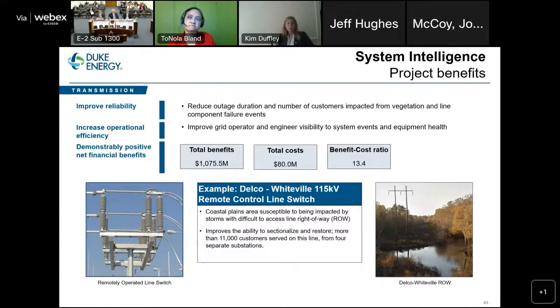When we have a lightning strike, a tree coming down on a line, a component failure, or a structure failure during a weather event like a hurricane, it's very difficult to access and restore. By having these remote-operated switches, we can tighten up the faulted segment of line and restore customer load faster. This specific project improves reliability for more than 11,000 customers directly served off this transmission line, from 4 separate substations.